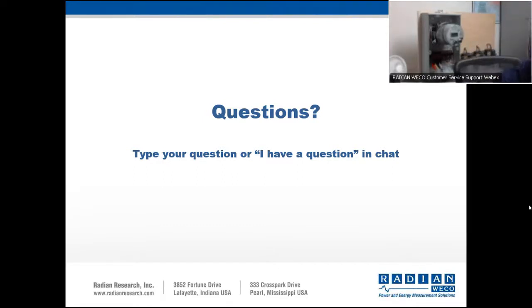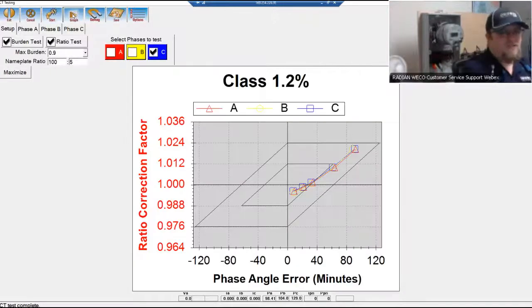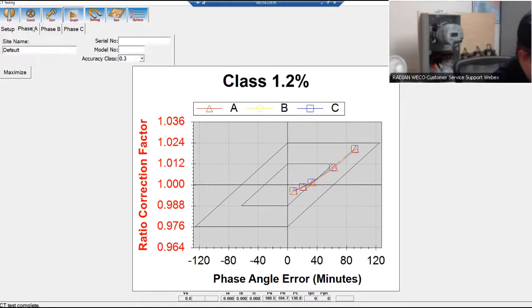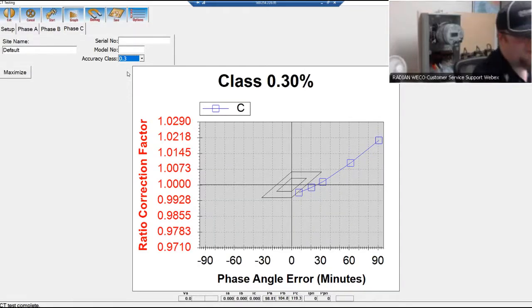Can you show the results in graph performance? Absolutely. Let me bring that up over here. So this is the parallelogram graph that I got based on my A, B, and C phase CT test results. Granted, this is for the class 1.2 because I only typed in the 0.3 on A phase, and the rest being blank. So it's erroring out on me. So if I change that back to 0.3, you can see that even this is a little bit outside of that typical parallelogram.